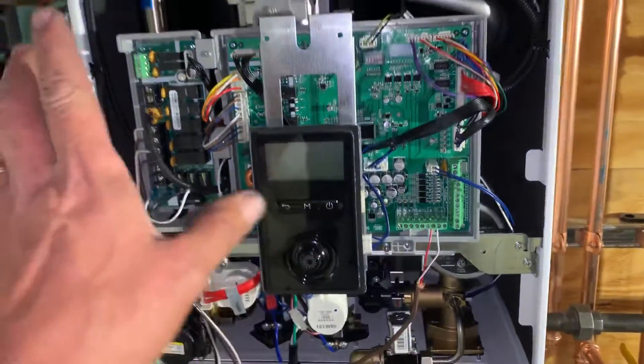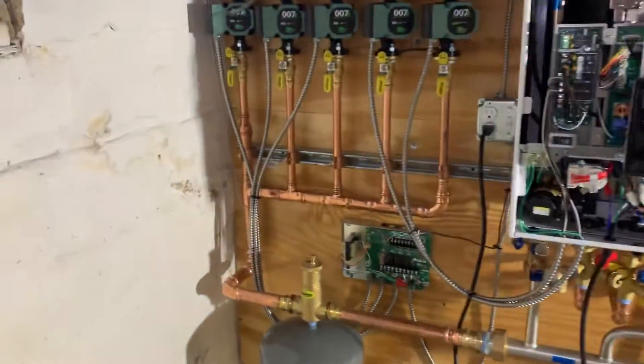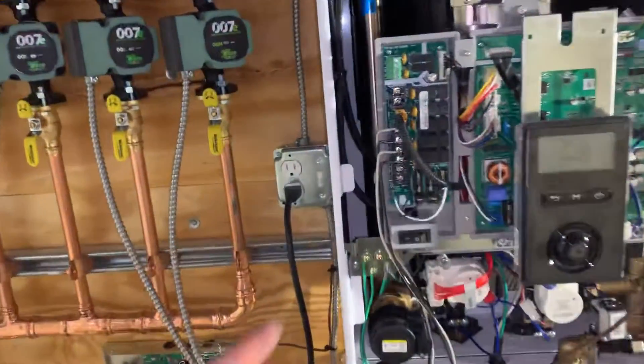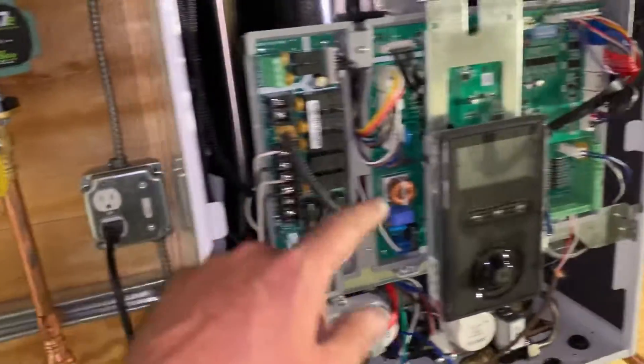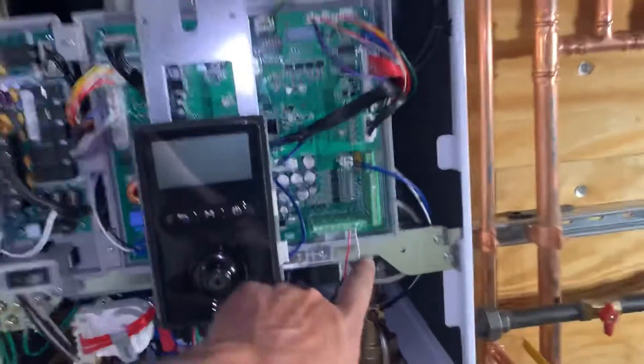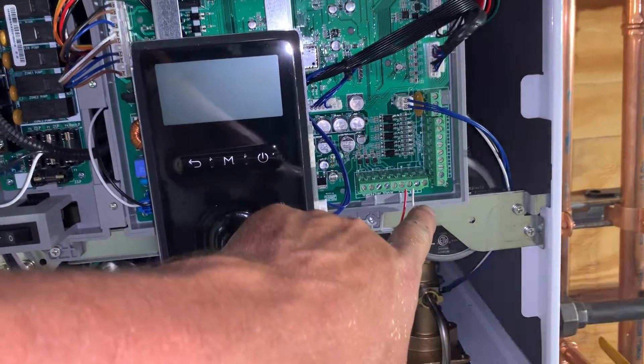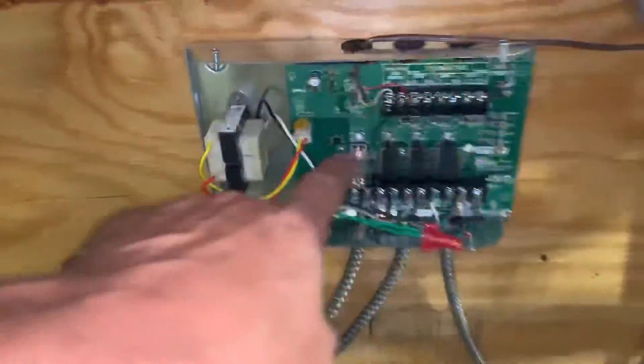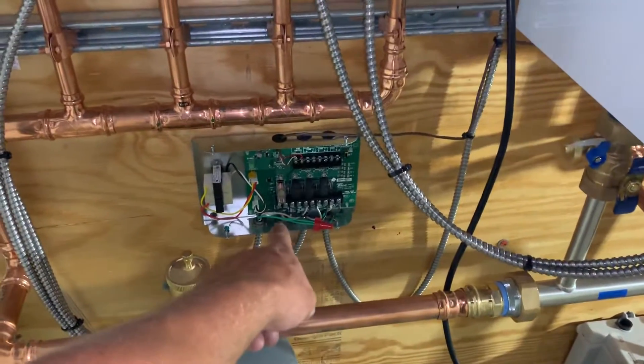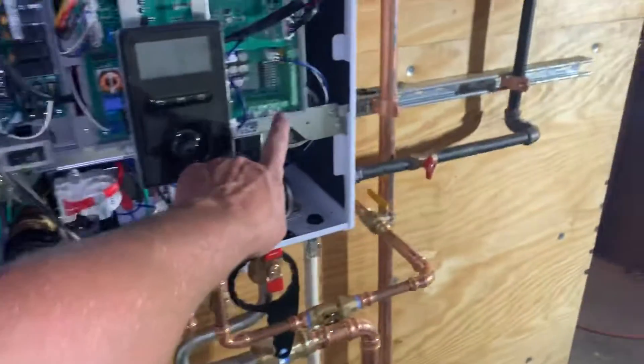Now the Navien NFC models come with the ability to wire three zones directly to the internal circuit board. If you're going to add more than three zones — like in this case, five — you're going to use two of the onboard zones, one and two, and for the third you're going to take the R and the W and bring that to TT on your relay. That way, when one of the three zones on this relay energizes, it's going to tell TT to turn on and the system will run.